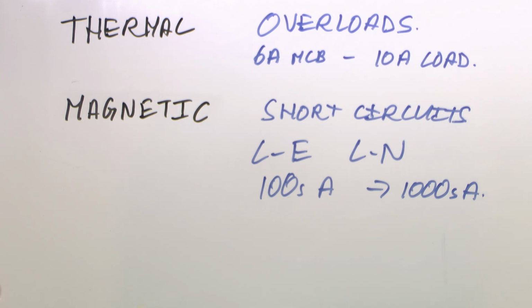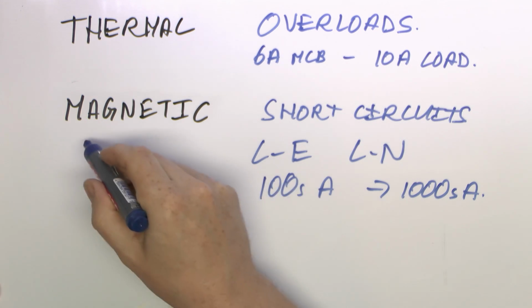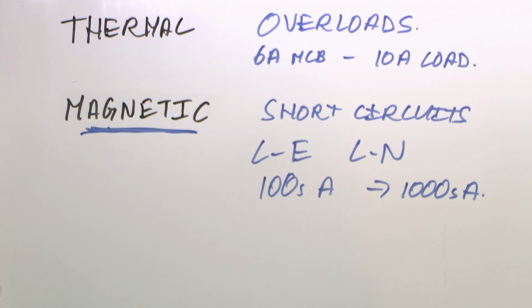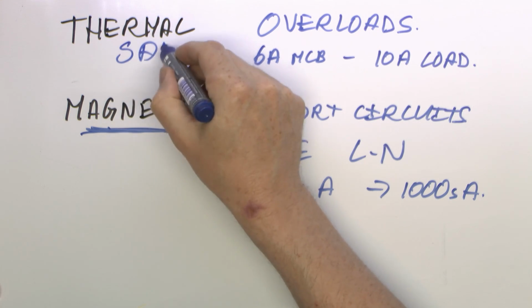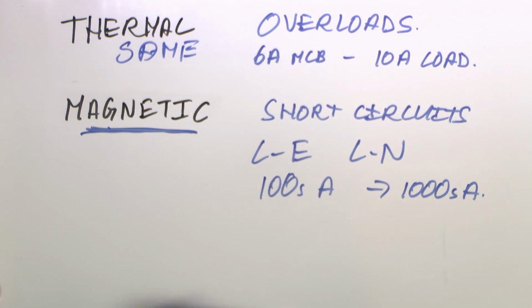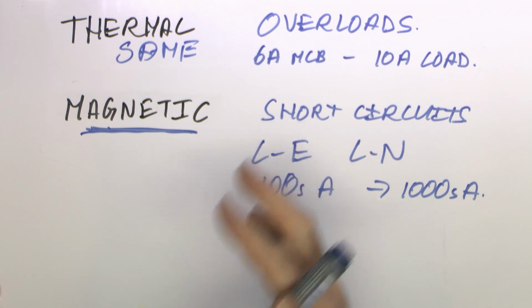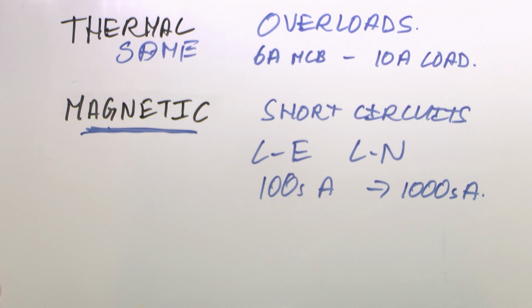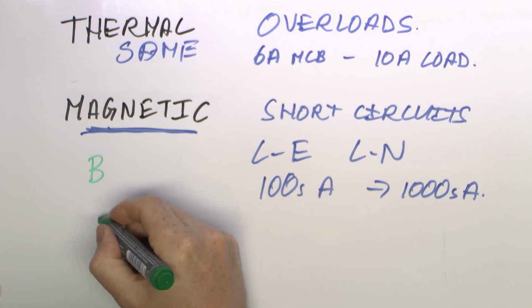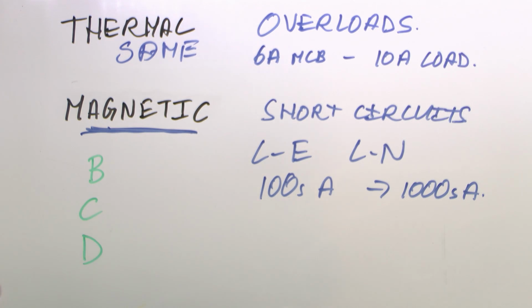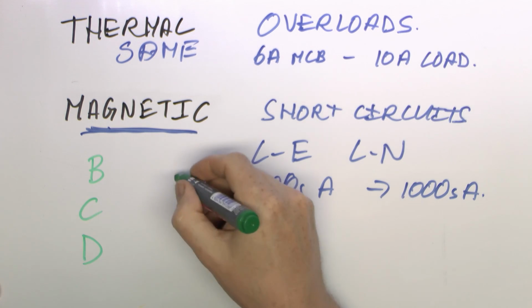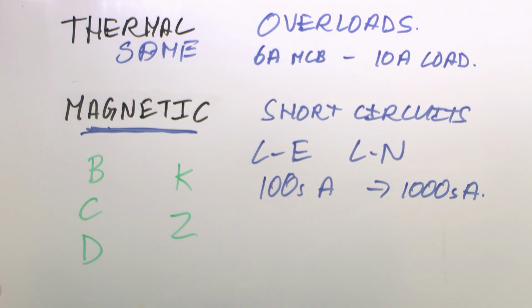Now, for the types of circuit breakers you can get, B, C and D being the most common, this only applies to the magnetic part. The thermal part is actually the same regardless of the type that you've got. So we're only talking about the magnetic part here. The thermal overload part in there is going to be the same in any particular type you have got. And the most common types available are B, C and D. Now, there are a couple of others which are K and Z, but those are fairly uncommon, and certainly B, C and D are the ones you're going to find in most applications.